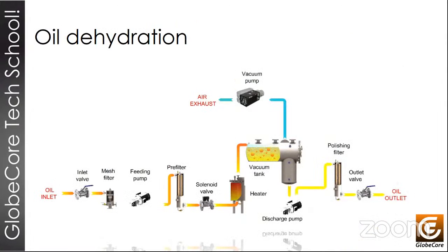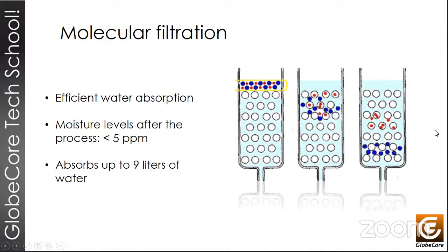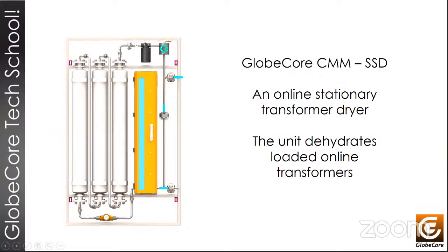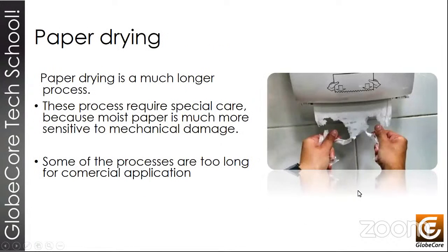The dehydration process is very similar for all manufacturers and brands, because it's pretty simple. But generally, if you follow the flow of oil from left to right, you'll see that the oil goes into the inlet. It passes through a coarse filter or mesh filter that filters out really large particles. Then it goes to the inlet pump. That pump's usually mounted before, for instance, a 25 micron filter. And then oil goes into a heater. It's heated to a temperature of about 65 degrees to prevent oil decomposition. And then this hot oil is fed into a vacuum chamber. Back, please.